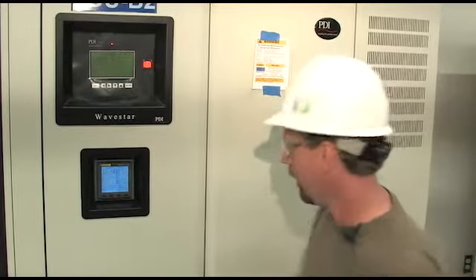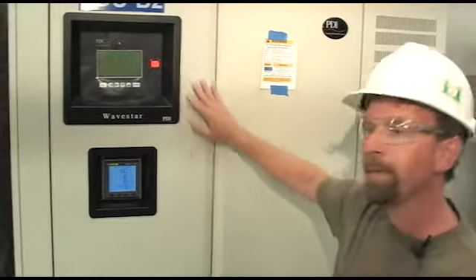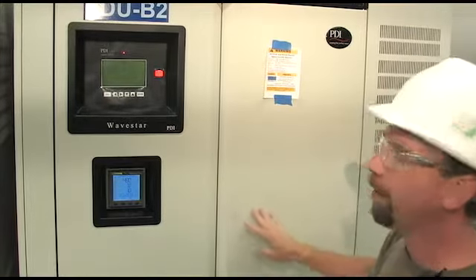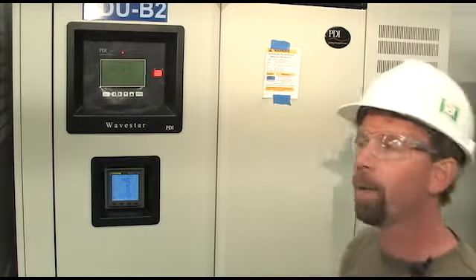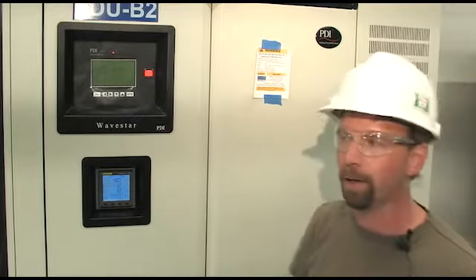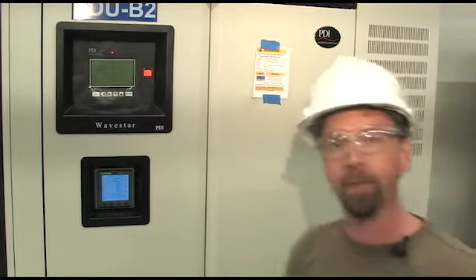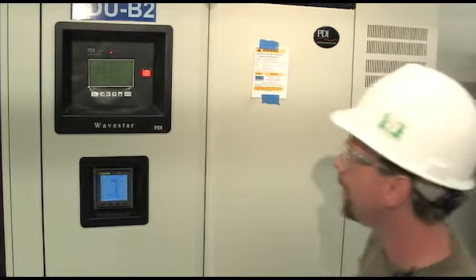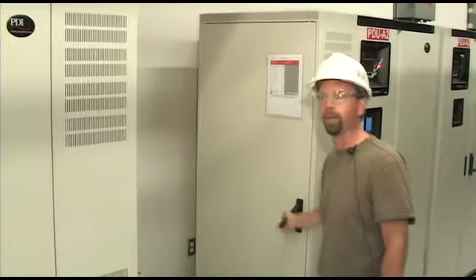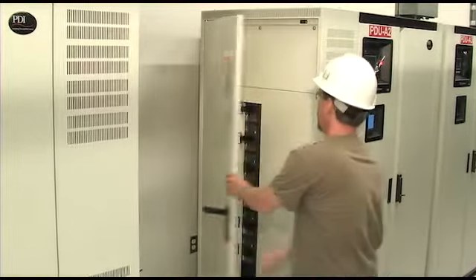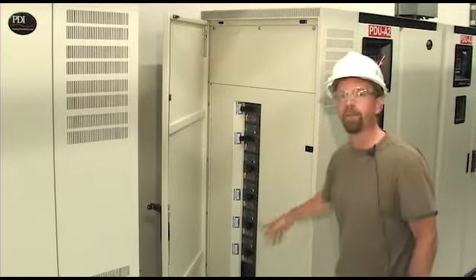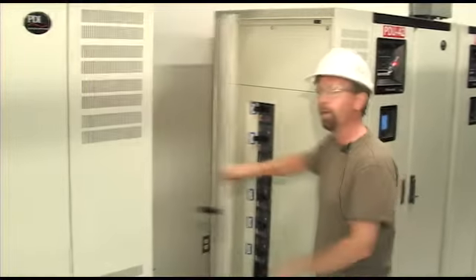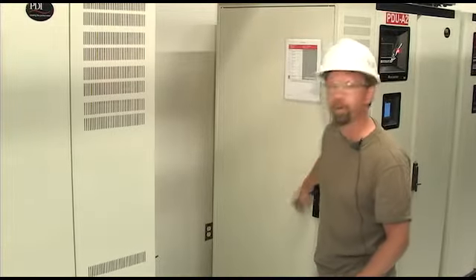This is basically a monitoring panel board system, and what we have basically is a display. There's a transformer inside this. It's taking 480 in and transforming it to 208 out, and it's monitoring all the circuits associated with the output downstream. And I'm going to show another unit over here so you can see the breakers. Basically the output is distributed out these breakers that go out to remote power panels. And those is where you're going to have your amperages monitored per circuit.